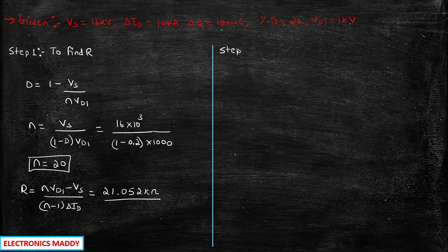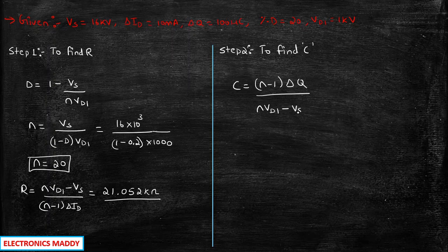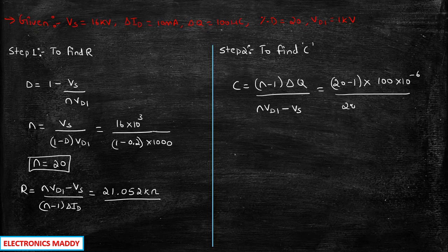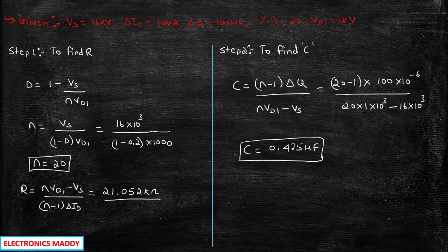Step two is to find the value of C. The formula is: C equals N minus 1 into delta Q, whole divided by N into Vd1 minus Vs. Substituting N equals 20, delta Q equals 100 micro coulomb, Vd1 equals 1 kV, and Vs equals 16 kV, and solving, you will be getting the value of C equal to 0.475 microfarad. So we have found both R and C, which is our requirement. Problem 3 is done.